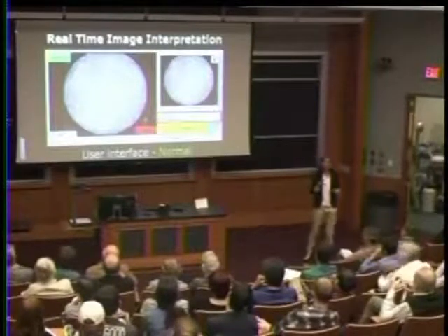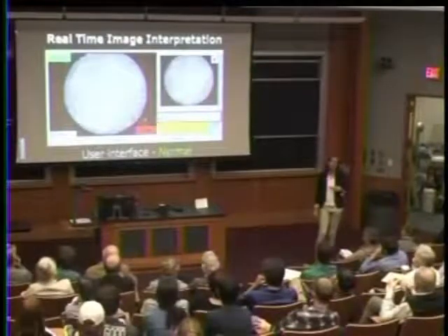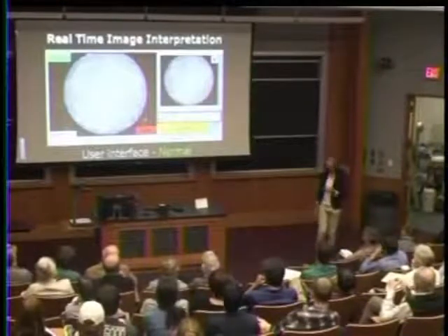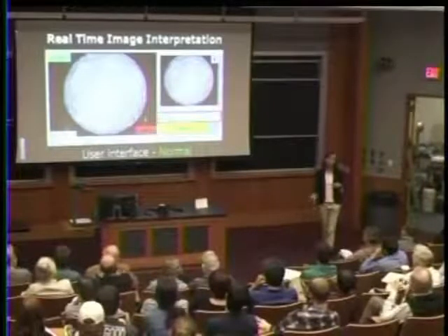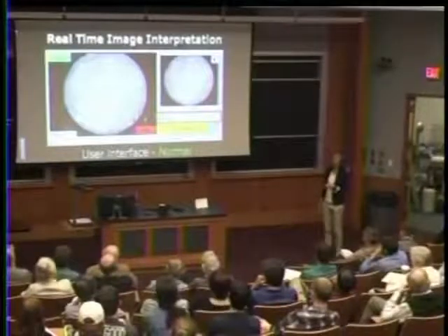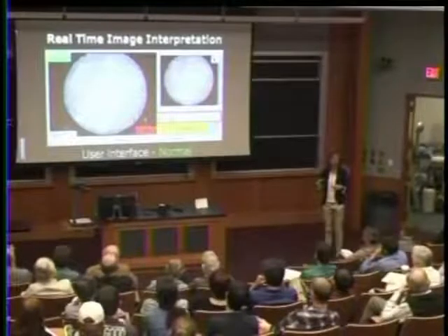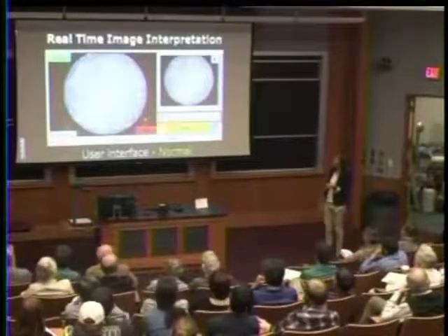When the physician is satisfied with the image, they press a foot pedal, and then the image is processed in a procedure that takes about a second. The nuclei are segmented, and we identify any that are abnormal based on their size and shape. The abnormal ones are outlined in red, and then we calculate the fraction of nuclei that are abnormal. If it's below a threshold, this bar is green.